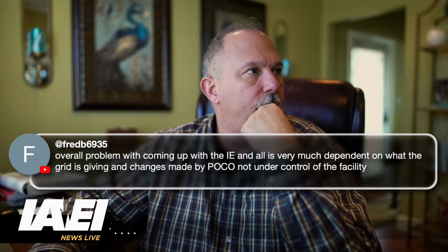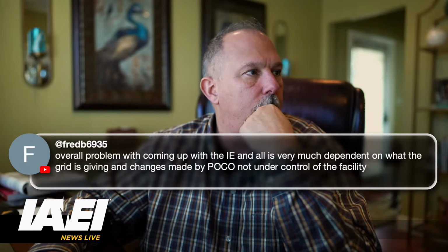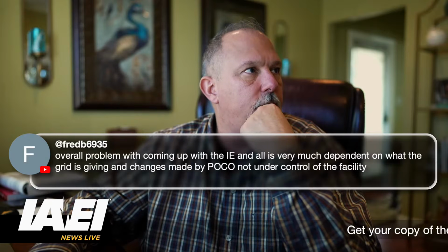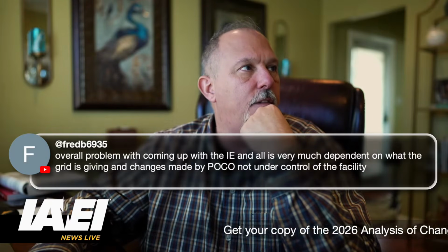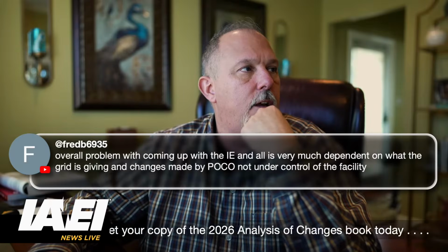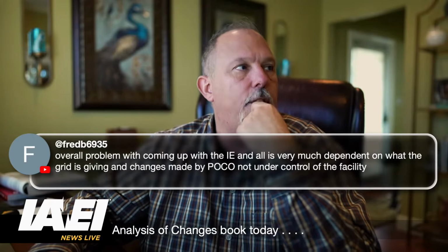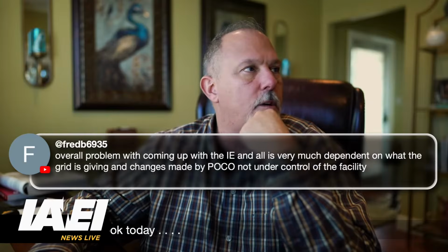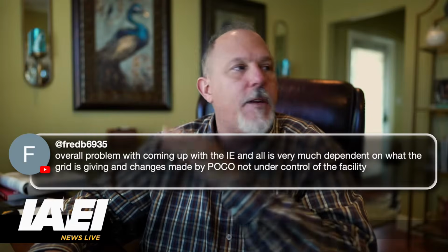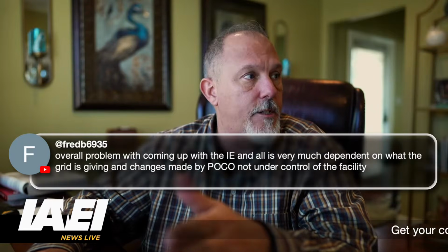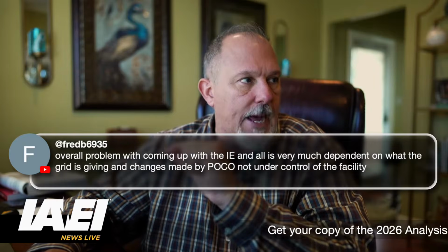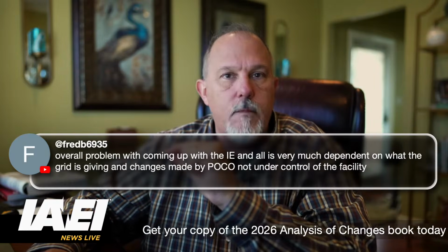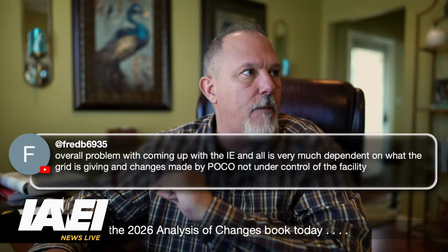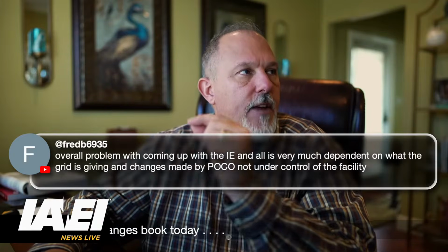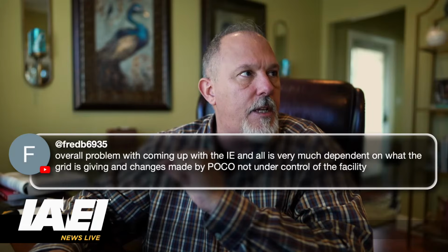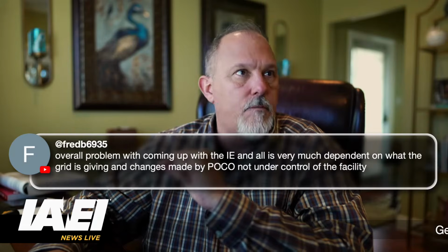I do have, if you change the fault current on the primary of a transformer, you've got to have a very big swing in available fault current to impact the secondary available fault current. Your secondary available fault current is going to be pretty stable.